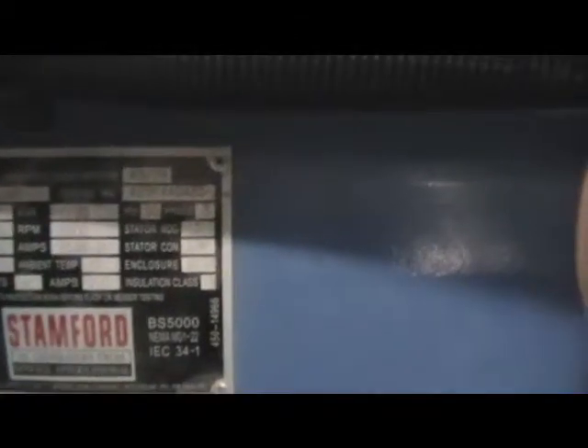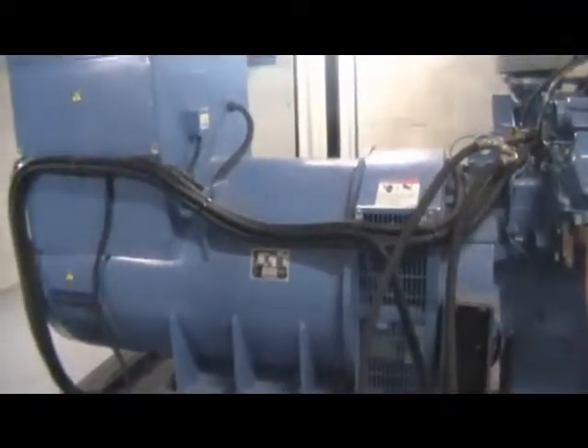So what are we looking at here per power plant? We've got a 400 volt generator, capable of 1600 amps at 1500 RPM. So we're talking about 1.1 MVA per alternator, and you've got 4 of them.